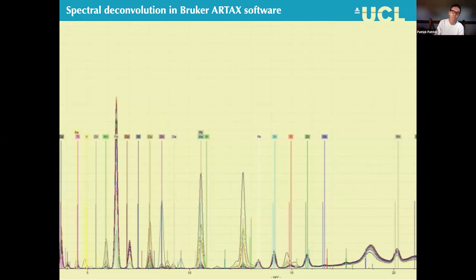Unfortunately, this is a bit of a fuzzy screenshot, but this is me following his instructions in Artax and deconvoluting the data. To check the efficiency of it, so that it improved the performance of the soil mode that comes with the machine, we analyzed certified reference materials. These are ones that Detlef supplied in mylar film or polypropylene film and powdered in these cuvettes, and still got these of various standards with trace element values in them. So to check it, and it did improve it.